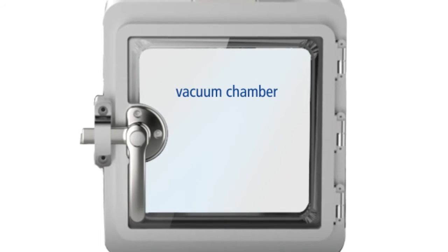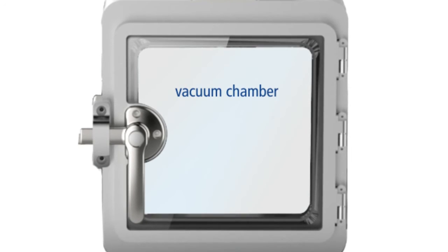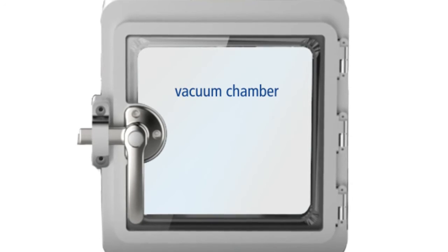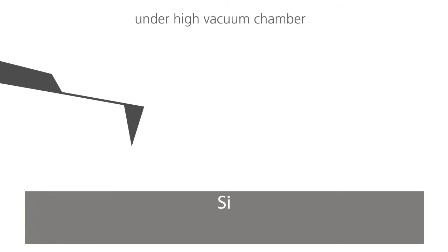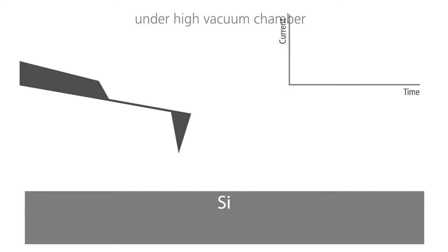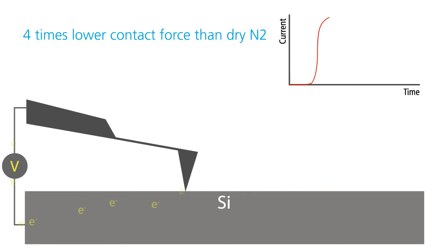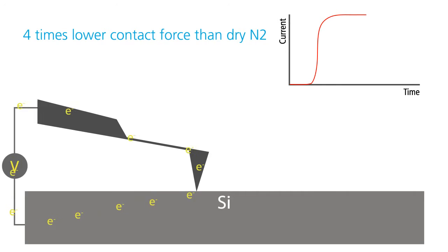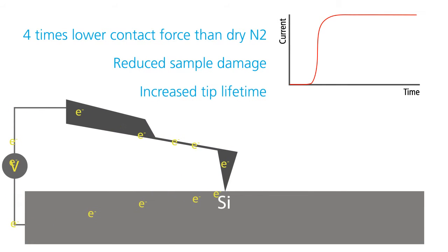AFM measurement in a high vacuum environment addresses these issues head on. Oxidation is prevented in the absence of ambient air, which in turn decreases by 4 times the tip-sample force load compared to alternate processes using dry nitrogen environments.